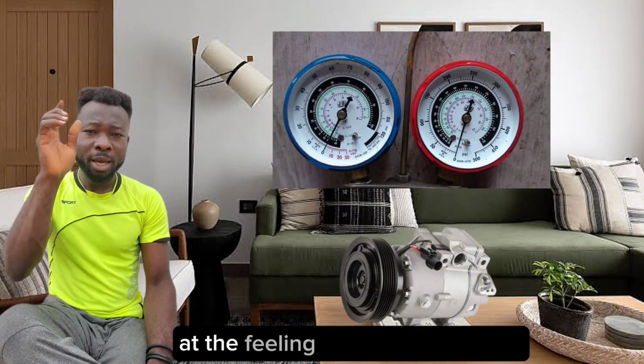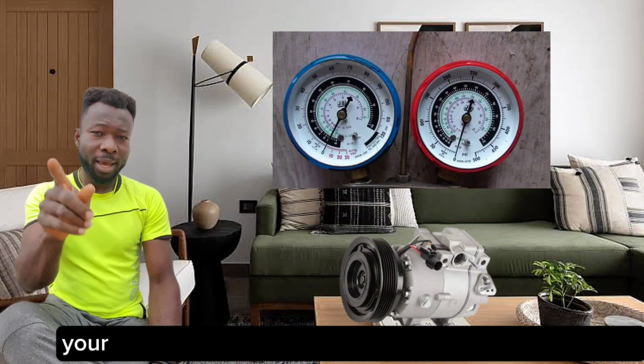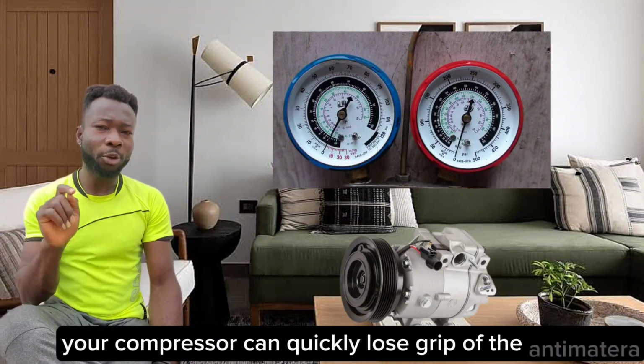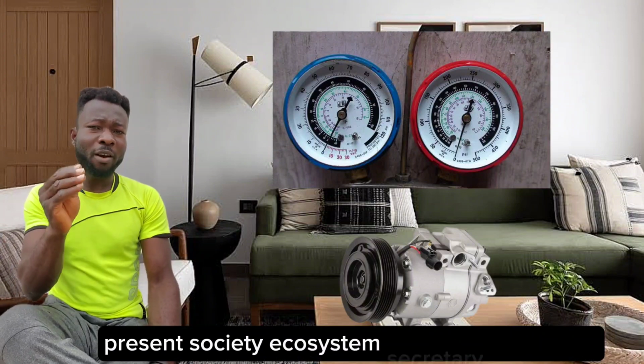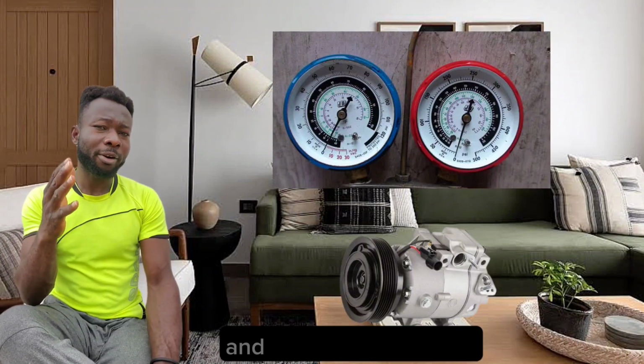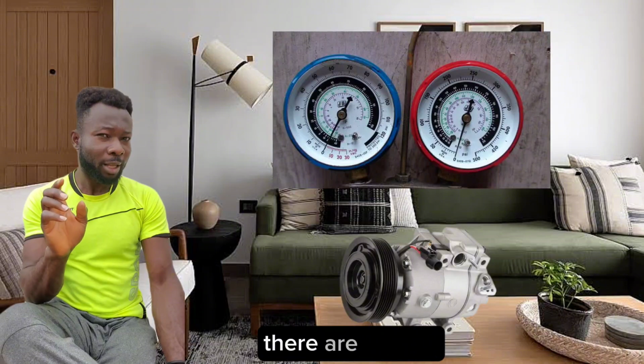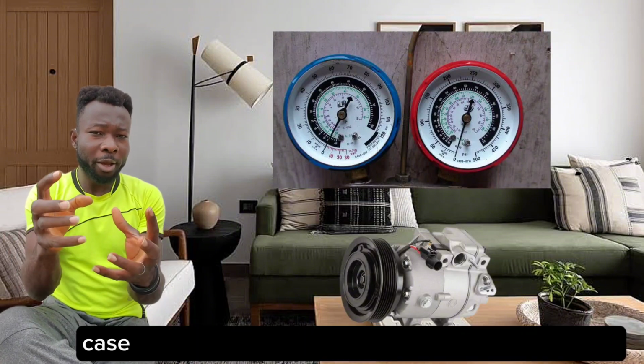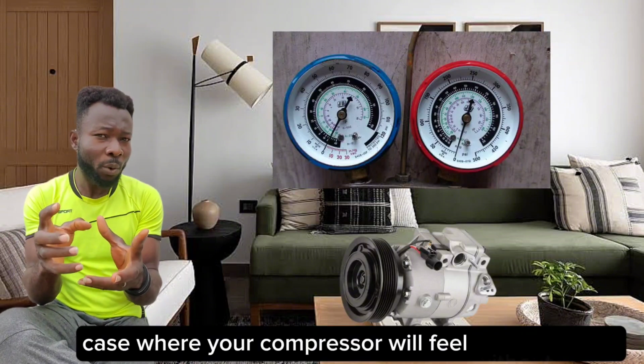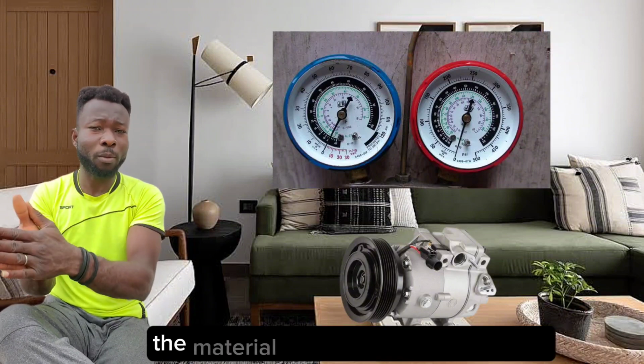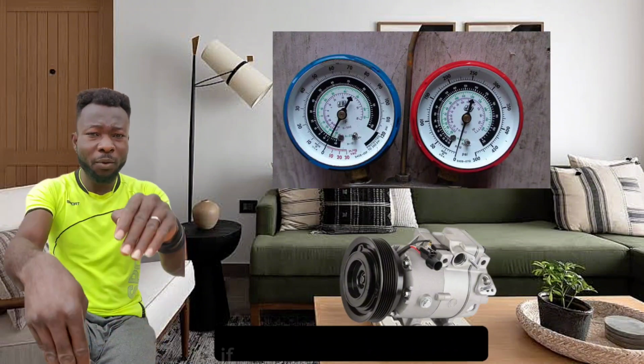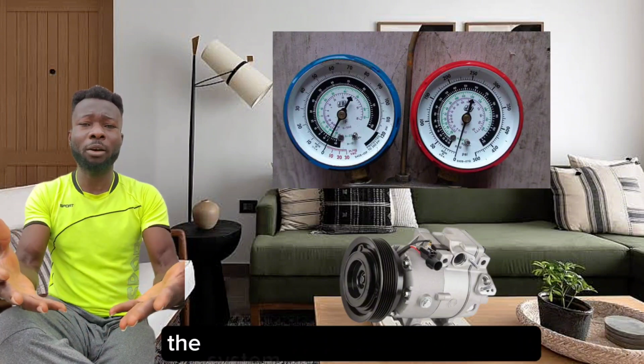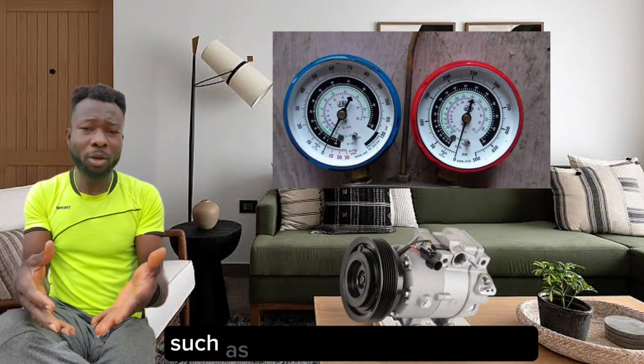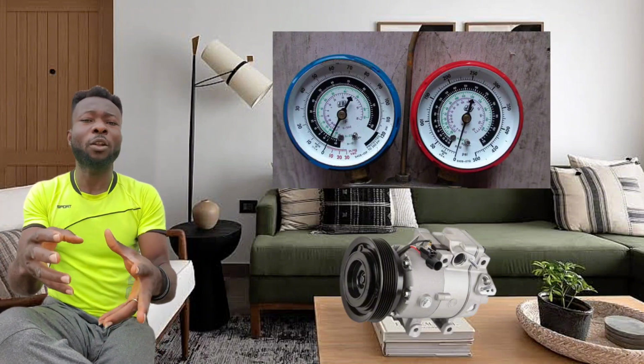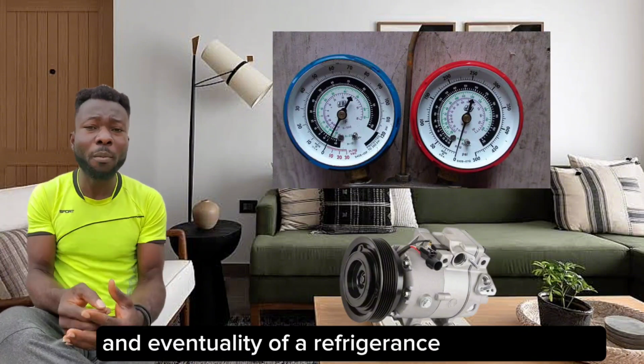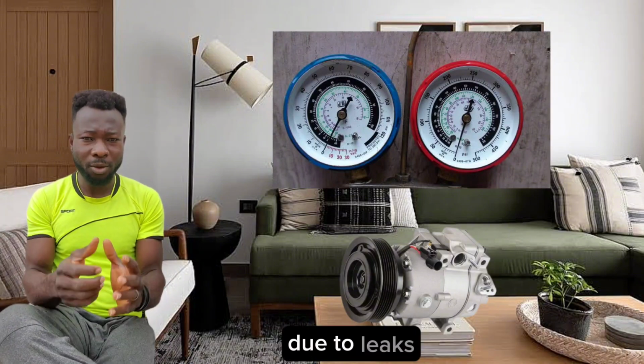At the failing of your compressor, it can quickly lose grip of the entire material present inside the AC system circuitry, such as oil and refrigerant. However, there are several cases where your compressor will fail without losing the material present inside the system. If left unchecked or resolved, the system will face more problems such as contamination by moisture and the eventuality of a refrigerant disappearance due to leaks.